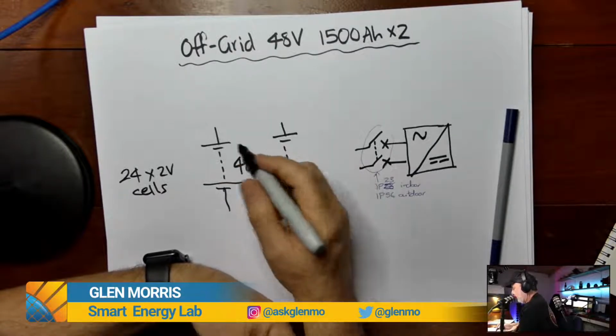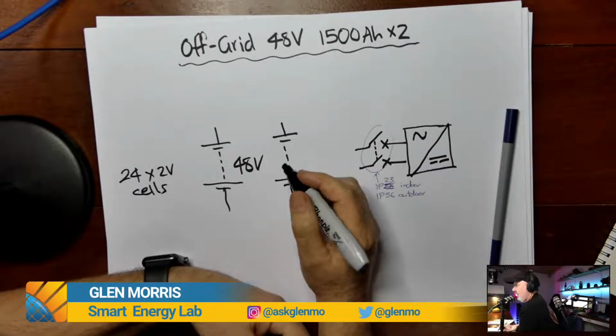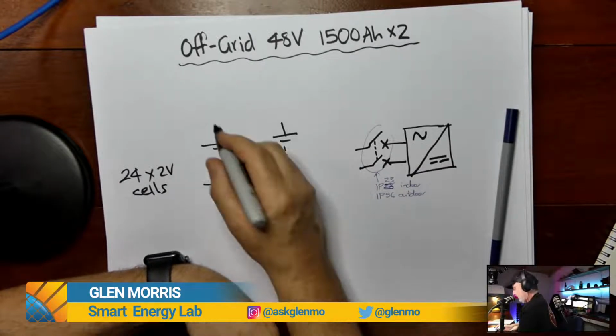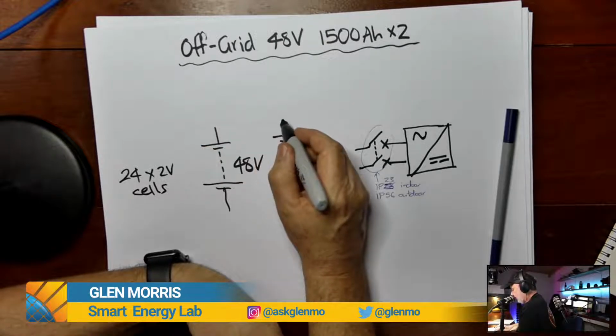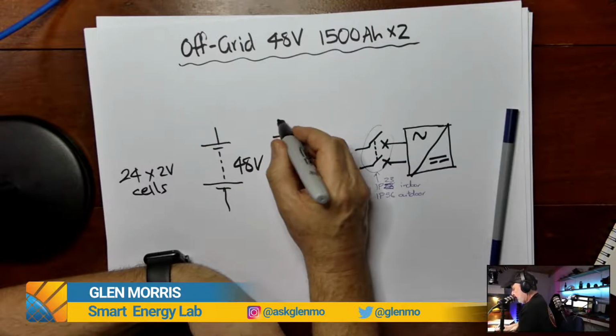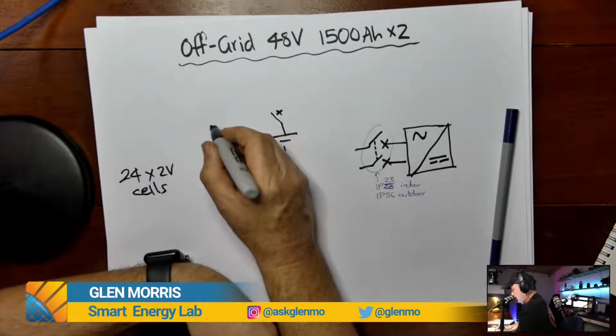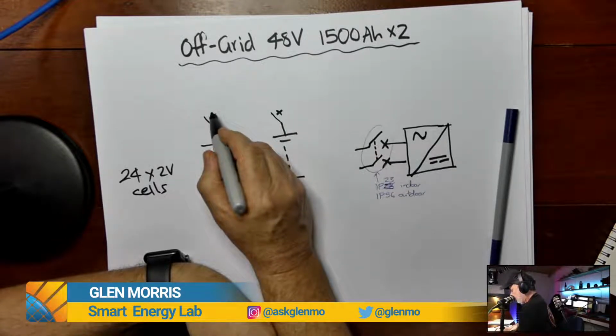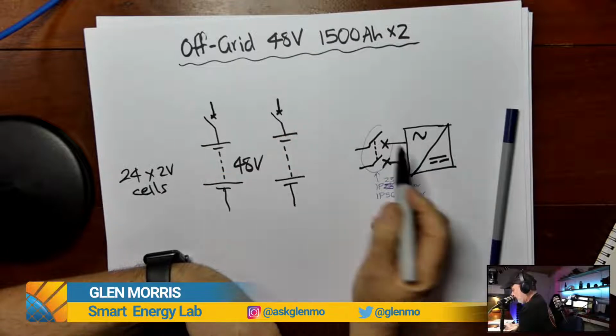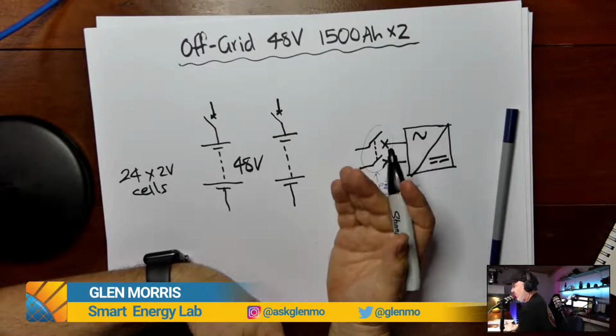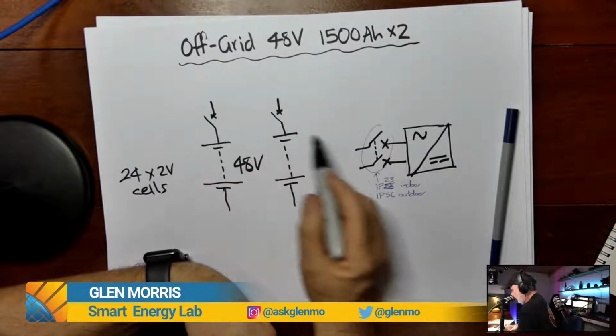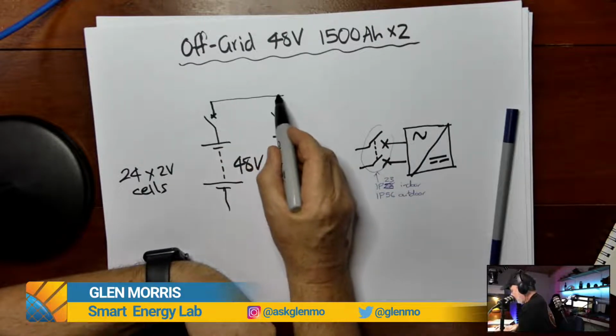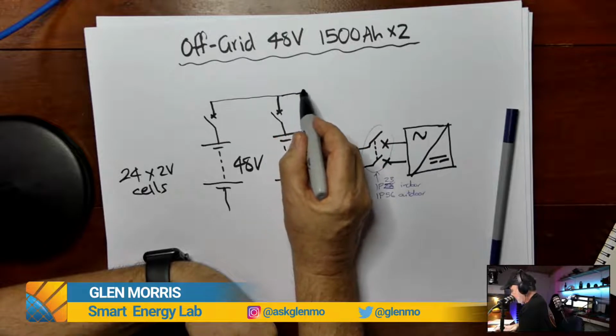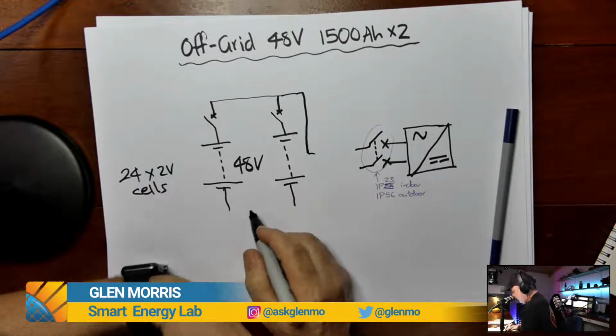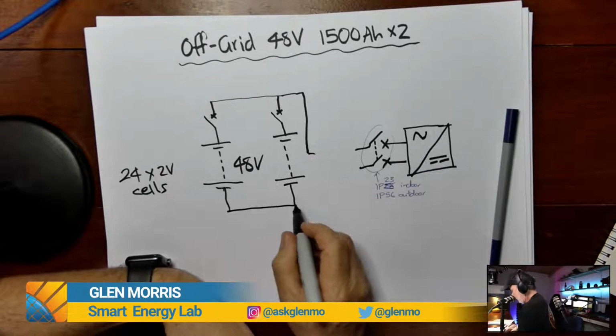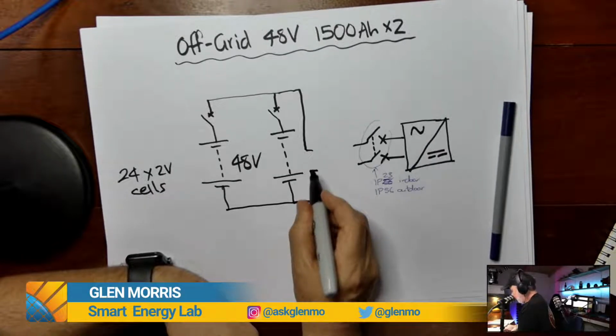So the requirement now is where there is more than one string of cells connected in parallel, you need to have overcurrent protection. So you could have a fuse, you could use a device such as a circuit breaker, but anything that provides overcurrent protection. So there we go. So there's our string overcurrent protection. It only has to be on one pole, it doesn't have to be on both. Now we could connect those straight to the inverter, but one of the considerations is distance. How far from the battery system is the PCE?